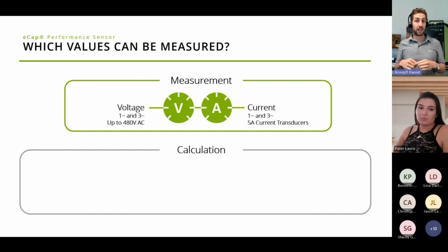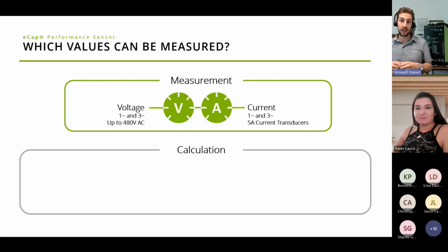You also connect directly to the product a single or three phase current path through 5 amp current transducers. Those could be split core or solid core transducers, so you can scale for smaller applications, but could go as high as, for example, 2000 amp motors.